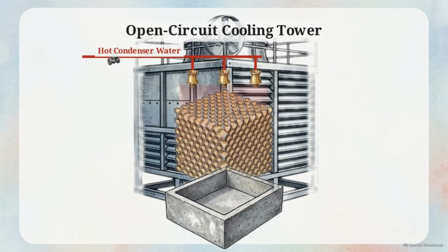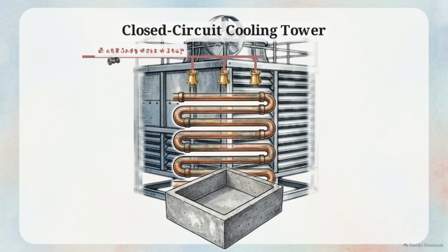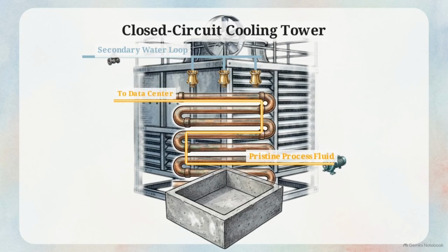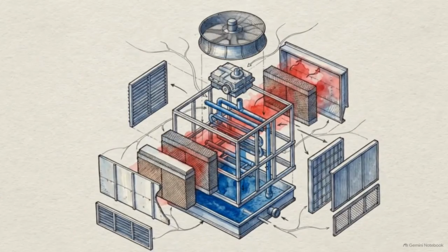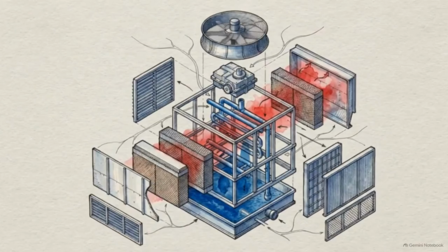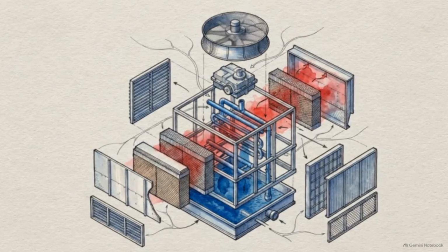Beyond airflow, engineers must also consider the working fluid itself. Using the atmosphere for cooling inherently introduces the risk of contamination into the condenser loop. Most commercial buildings use an open-circuit system. The hot condenser water is sprayed directly over the fill, exposing the primary loop straight to the outside air. However, if the process fluid must remain pristine, a closed-circuit system is used. The fluid stays isolated inside a sealed serpentine coil, while a secondary, completely separate water loop sprays over the outside to cool it. Selecting a tower configuration is a strict engineering trade-off that balances thermal efficiency, footprint limitations, and maintenance accessibility.